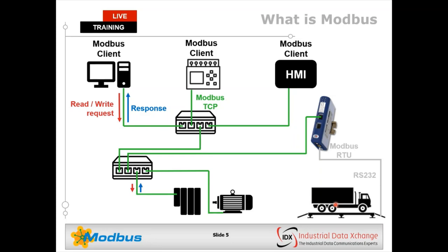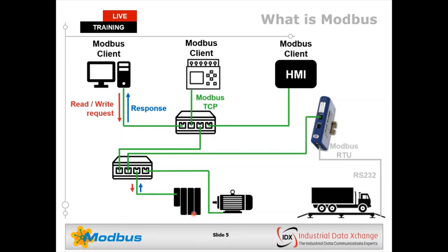It provides a client-server communication between devices — a request-response type protocol. A Modbus client initiates communication by sending a read or write request to any device in the network. That device receives the request and, if it can, responds with the information. Within Modbus TCP, you can have multiple masters interfacing with a single slave module. Modbus RTU is different — in Modbus RTU, you can only ever have one master on the entire network. That's very important.